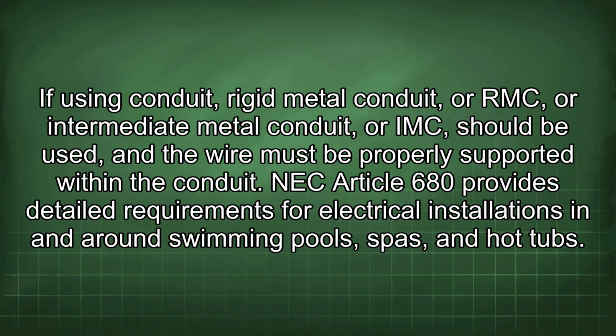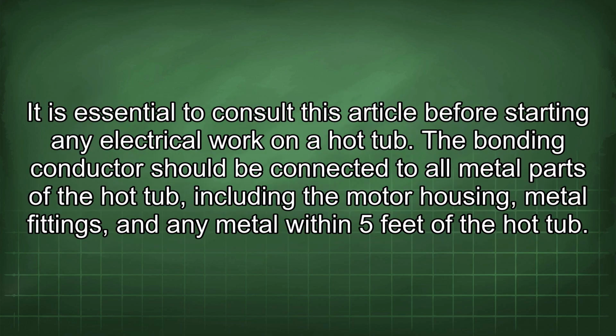NEC Article 680 provides detailed requirements for electrical installations in and around swimming pools, spas, and hot tubs. It is essential to consult this article before starting any electrical work on a hot tub. The bonding conductor should be connected to all metal parts of the hot tub, including the motor housing, metal fittings, and any metal within 5 feet of the hot tub.